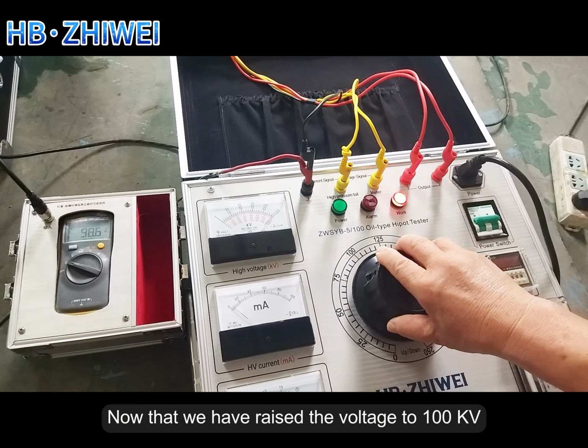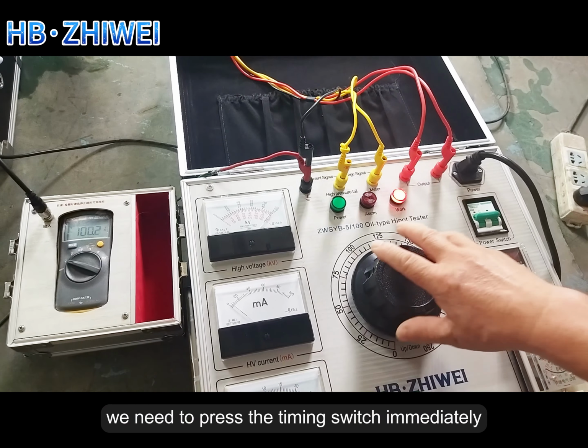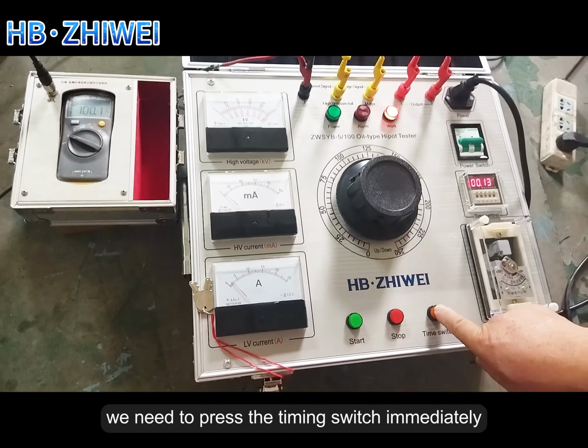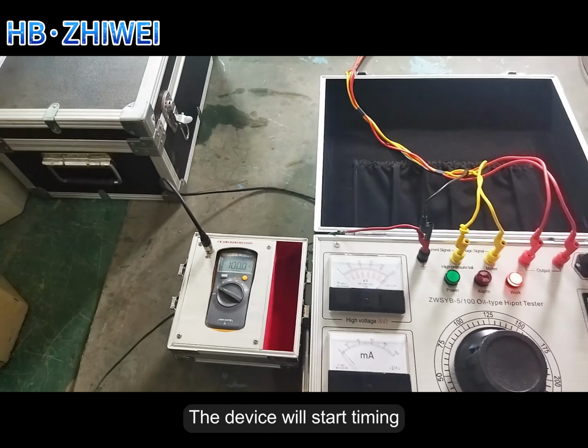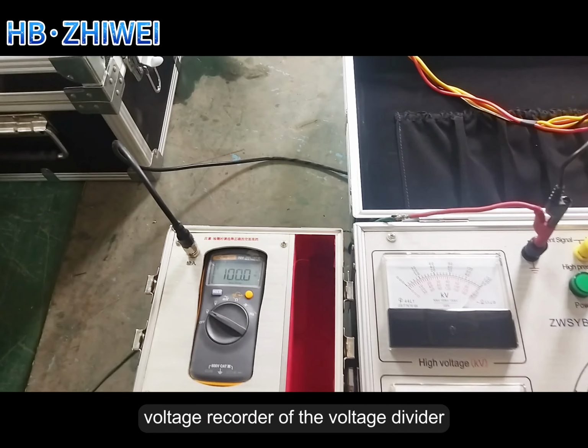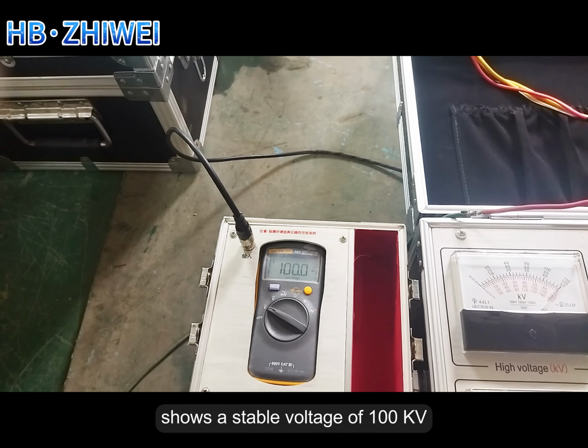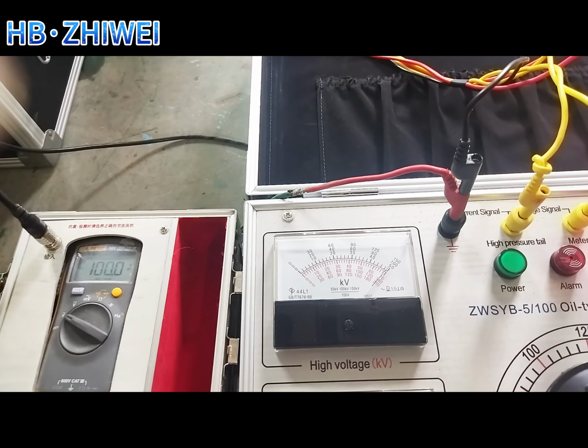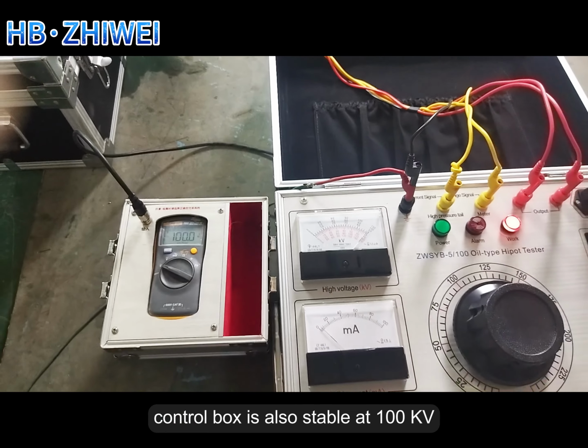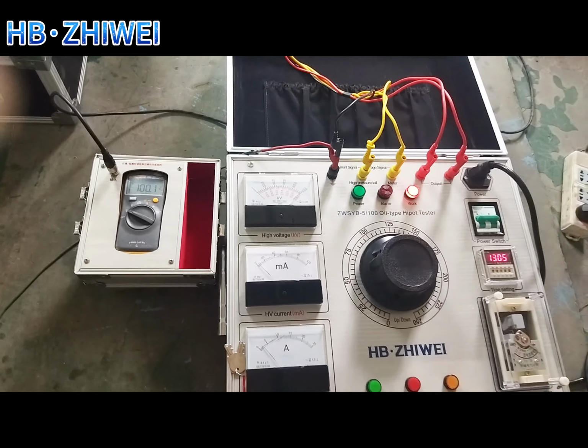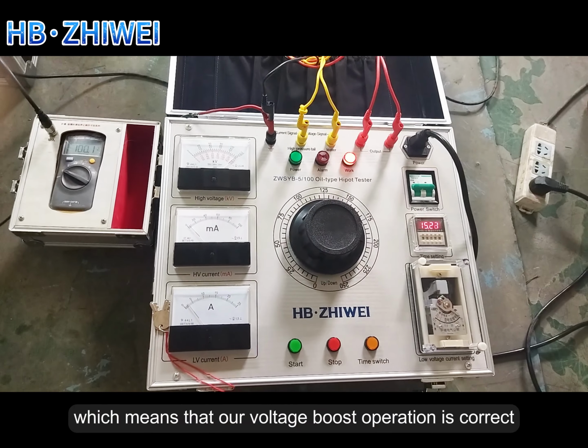Now that we have raised the voltage to 100 kV, we need to press the timing switch immediately. The device will start timing, and we can see that the voltage recorder of the voltage divider shows a stable voltage of 100 kV, and the pointer on the control box is also stable at 100 kV. Which means that our voltage boost operation is correct.